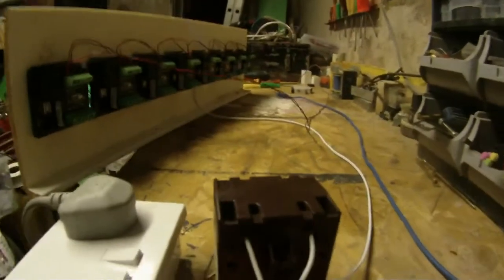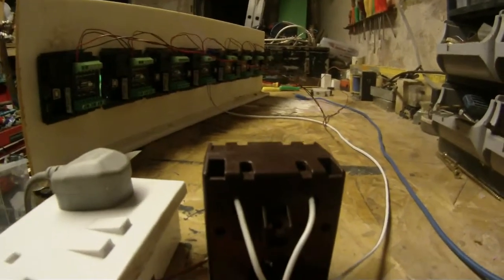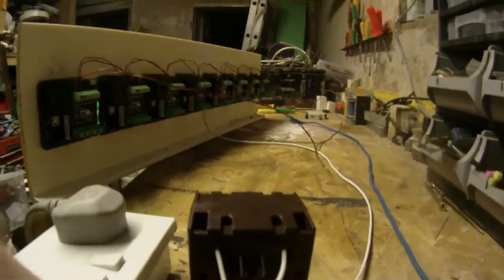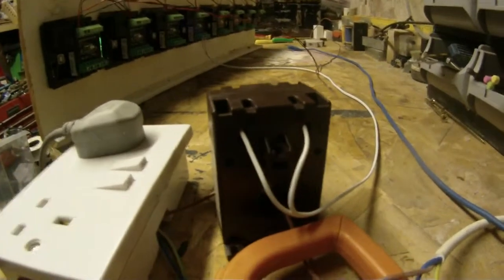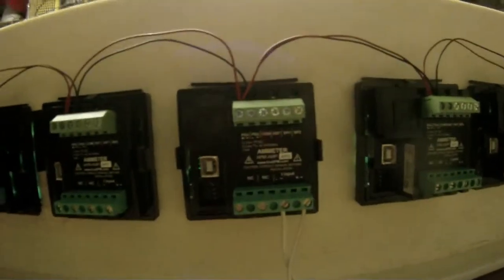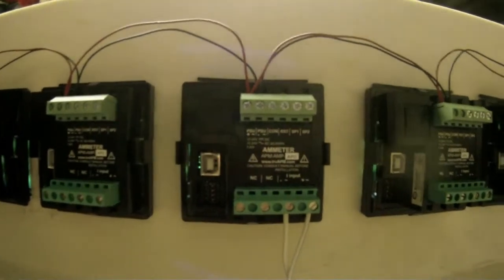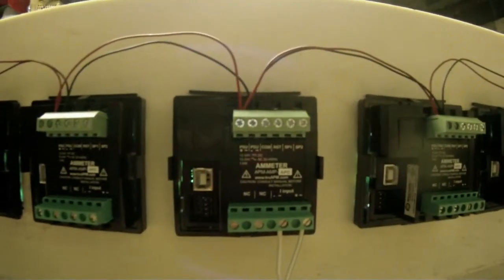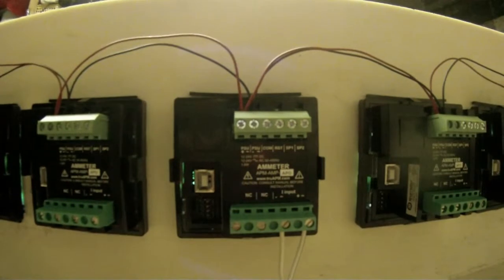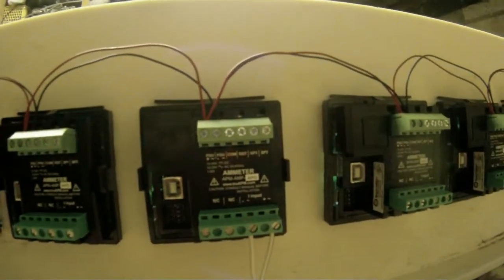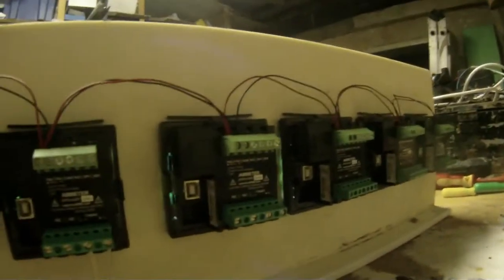Connection from the CT on the secondary is S1 and S2, obviously with the primary running from P1 to P2 at the other side there. That runs onto the input. And obviously we're using, or will be using, a 24 volt DC supply. That's just running off that AC transformer for now. Obviously those are just daisy chained across.